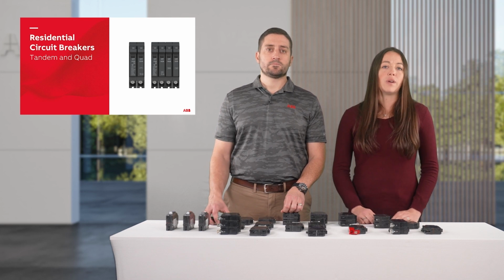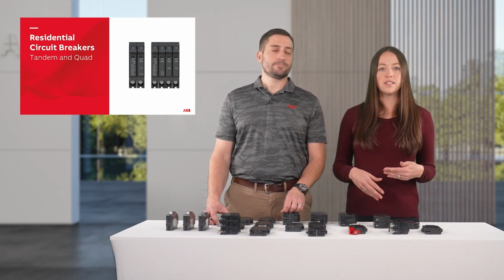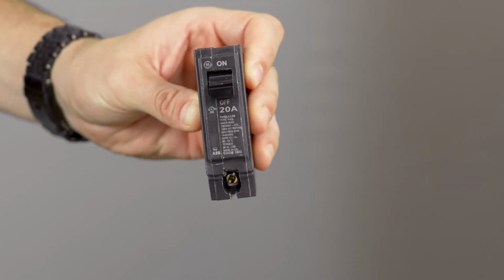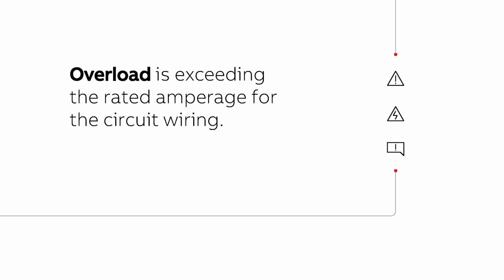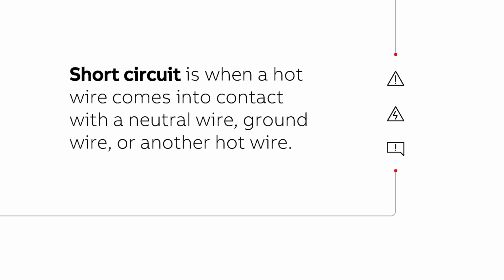We also offer a range of protections on our different breakers. First, a thermomagnetic breaker protects against overloads and short circuits. An overload is when the load connected to a breaker exceeds the rated amperage for the circuit wiring. A short circuit is when the hot wire comes in contact with either a neutral wire, ground wire, or another hot wire. If a thermomagnetic breaker detects either an overload or short circuit, the breaker will trip.